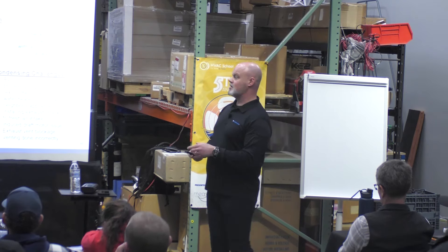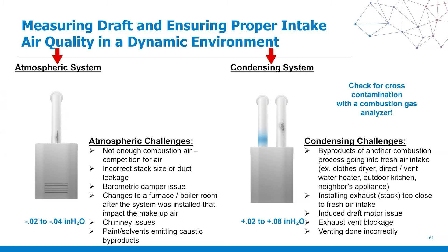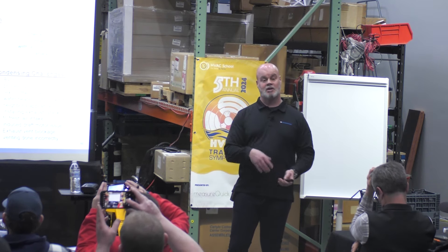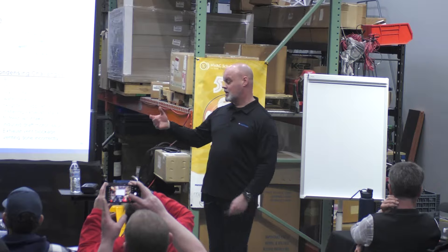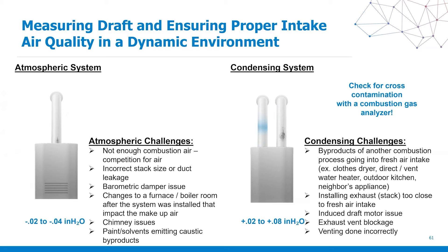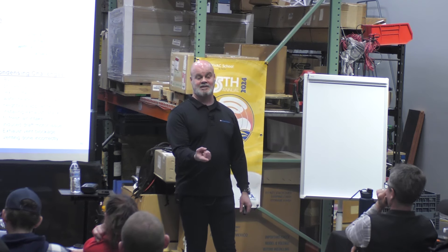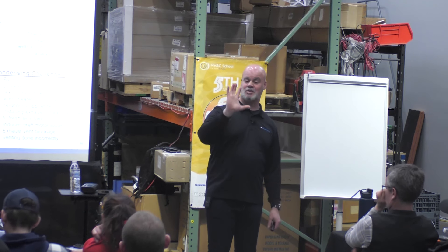An atmospheric system uses room air or make-up air for its combustion air. If you have a customer with one of these systems and they decide to make their furnace or boiler room into their office — they don't like the louver door and want a nice solid core door, making their office into a bank vault — we have a problem, because that system needs combustion air from the room.